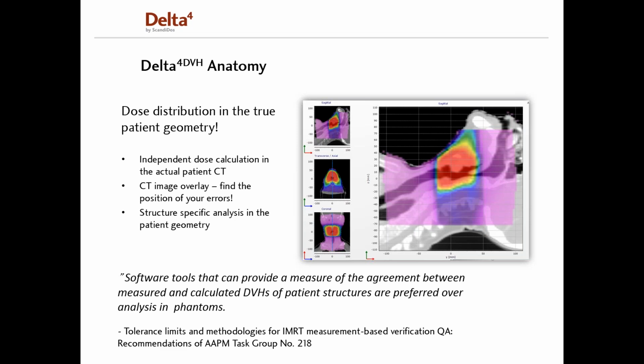The Delta4 DVH Anatomy software module calculates dose distributions inside the patient geometry using the measured values as an input, completely independent from the treatment planning system. Only by calculating the dose in the patient geometry can you get the actual dose that will be delivered to the targets and risk organs during treatment. And the Delta4 DVH Anatomy allows you to do this. So this software option includes visualization of the dose distribution overlaid on the patient CT, dose volume histograms of all structures outlined during the treatment planning within the patient geometry, and also structure-specific analysis within the patient geometry.